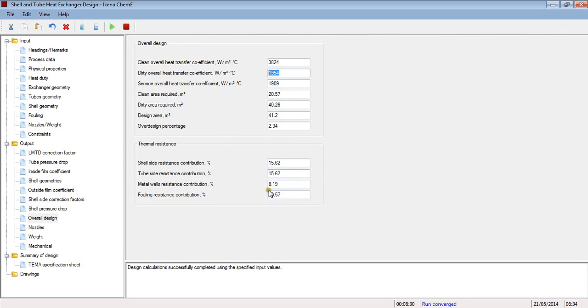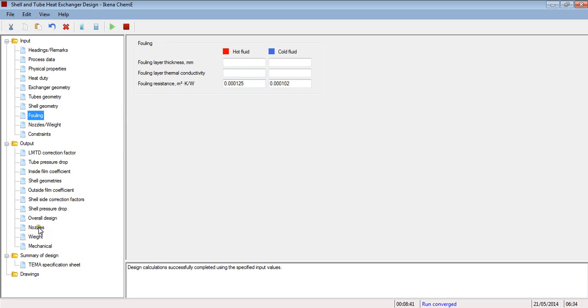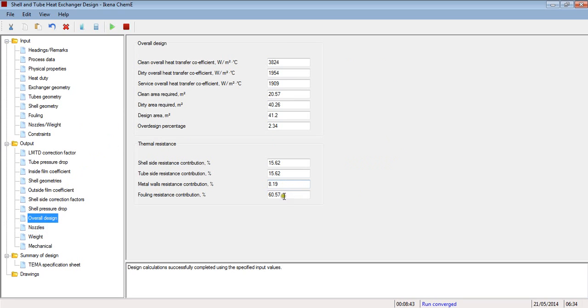And this part here shows you where your resistance is, where the thermal losses are. So as you will see over here, the most losses are due to fouling. This is the fouling resistance that causes over 60% of your thermal resistance. So what an engineer needs to do is work on trying to reduce fouling by using different techniques, by using fouling inhibitors or things like that. But we have identified that fouling causes the most thermal resistance here, so we will need to work on trying to reduce the fouling.